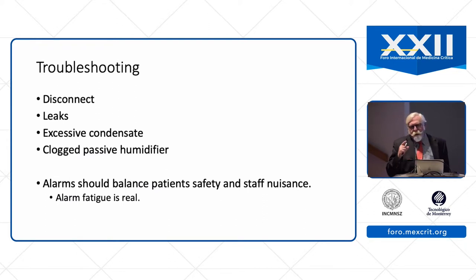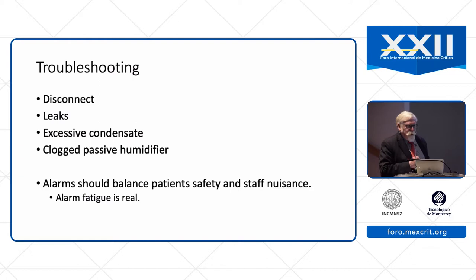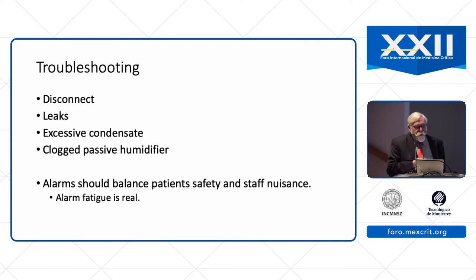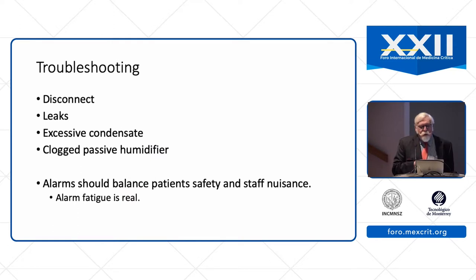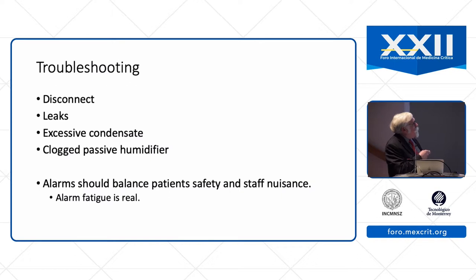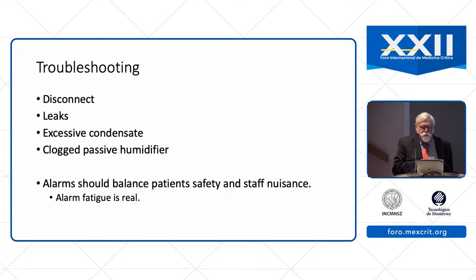We need to monitor both the inhaled and exhaled tidal volume because any difference between those will be the result of leaks that need to be corrected so that ventilation is not impacted. If we are using a heated humidifier, we need to monitor the circuit for excessive condensate and clear it from the circuit on a regular basis. If we are using a passive humidifier, we need to evaluate that for clogging with secretions, as the passive humidifier can become occluded in patients with a lot of secretions.